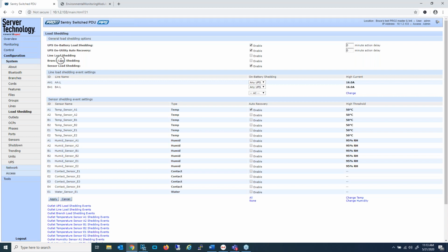The next item to look at is branch load shedding. And before I describe what that is, I should mention that we are logged into a PRO2 PDU. The PRO2 series PDUs measure everything there is to measure, and that includes measuring current through each of the circuit breakers in the PDU itself, and that is what branch load shedding is referring to. So you can set a threshold for current through each of the circuit breakers within the PDU. And if that current is exceeded, then we will switch off pre-selected outlets.